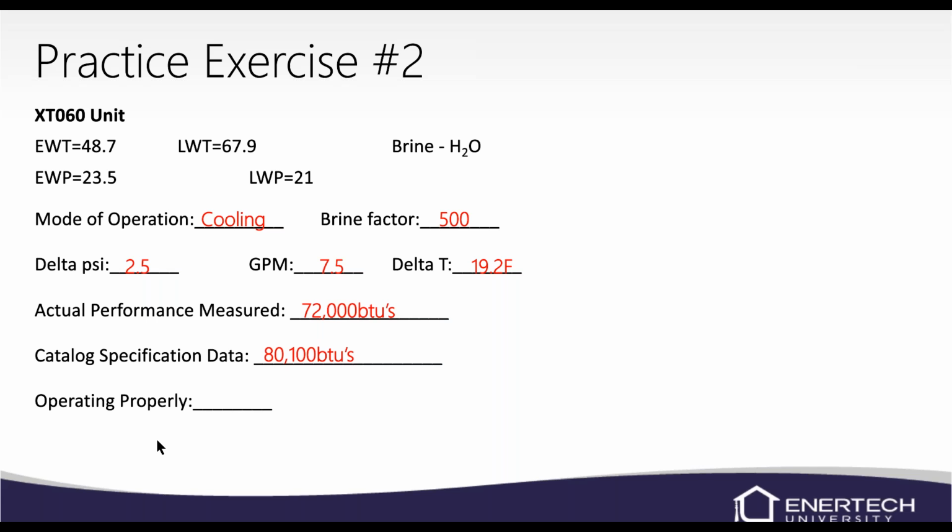So is the unit operating properly? Yeah, it is operating. It is within 10%, but it's real close. It's only about maybe 90 or so BTUs above that 10%. So on this example, there's a couple ways to look at it.